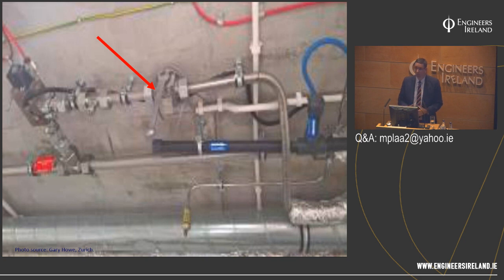And you can see it's a non-monitored valve. So it makes it even more important if it's non-monitored. But don't take it as read, even if it's a monitored valve. I will actually go to the valve and close it and open it and make sure we get a signal at the fire panel. And often there's been a miscommunication between the mechanical side of the project and the electrical side, where the fire detection contractor's done their bit and the mechanical guy's done their bit, and they haven't talked to each other. So actually go a bit further and get that valve closed and make sure you get a signal at the fire panel.